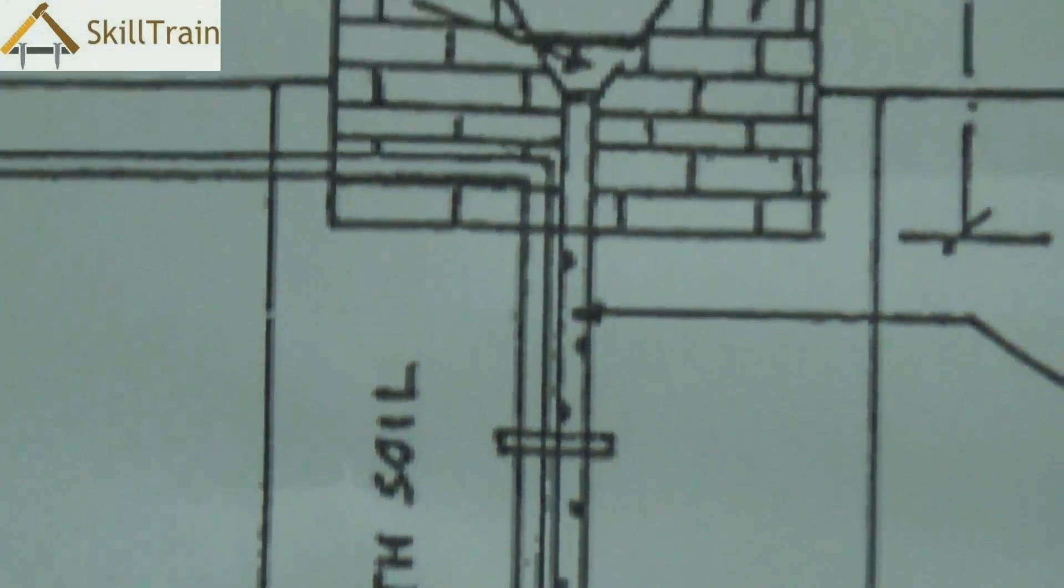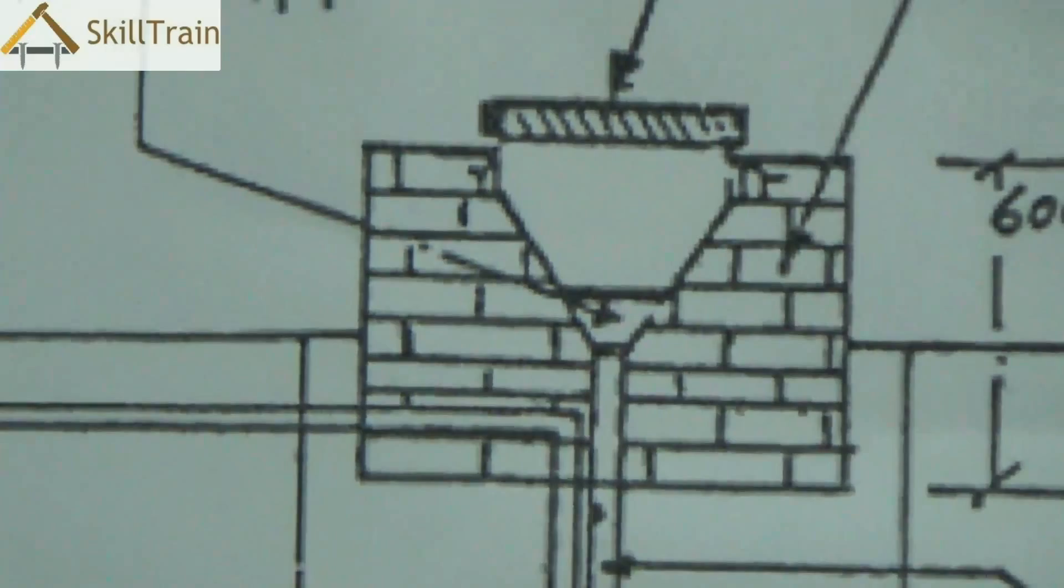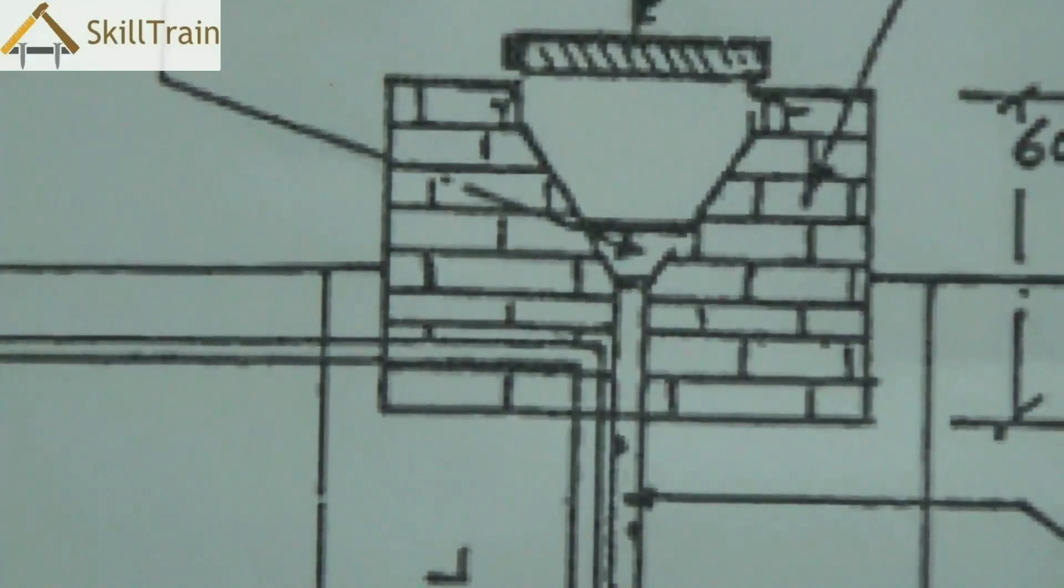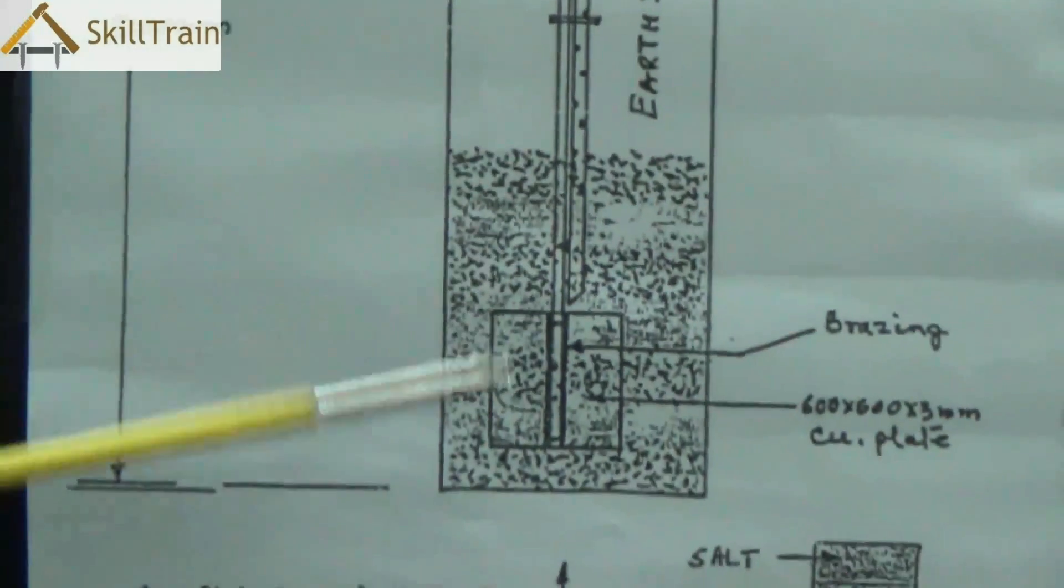The plate earthing requires water to be poured in to ensure that the humidity is maintained internally inside the pit and so regularly we need to open the pit and ensure that there is water poured into it to keep the humidity maintained inside the pit.